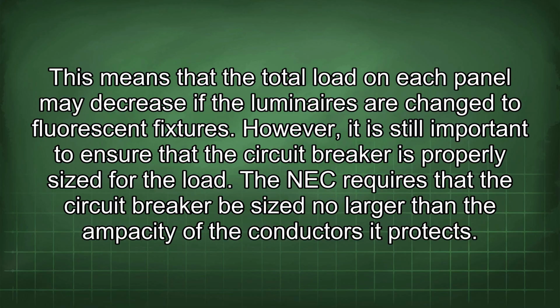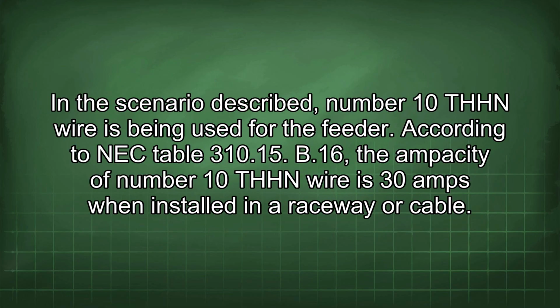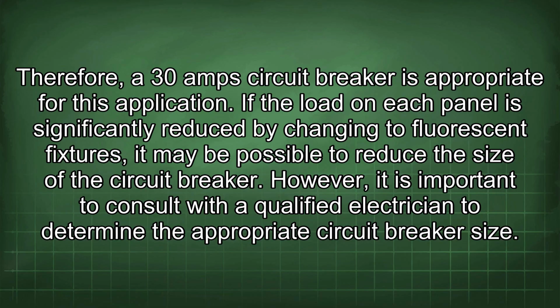The NEC requires that the circuit breaker be sized no larger than the ampacity of the conductors it protects. In the scenario described, number 10 THHN wire is being used for the feeder. According to NEC table 310.15(B)(16), the ampacity of number 10 THHN wire is 30 amps when installed in a raceway or cable. Therefore, a 30 amp circuit breaker is appropriate for this application. If the load on each panel is significantly reduced by changing to fluorescent fixtures, it may be possible to reduce the size of the circuit breaker. However, it is important to consult with a qualified electrician to determine the appropriate circuit breaker size.